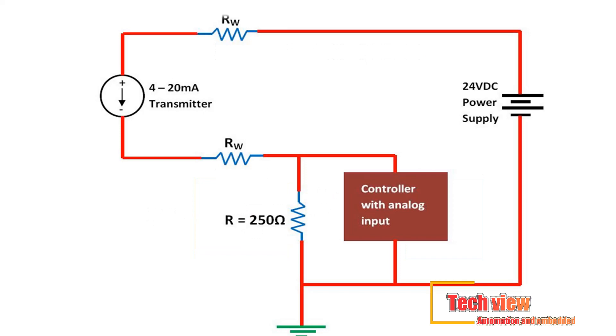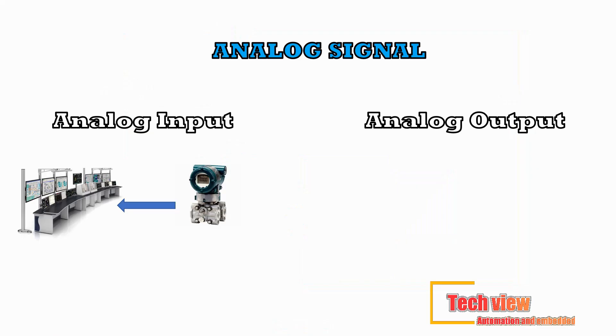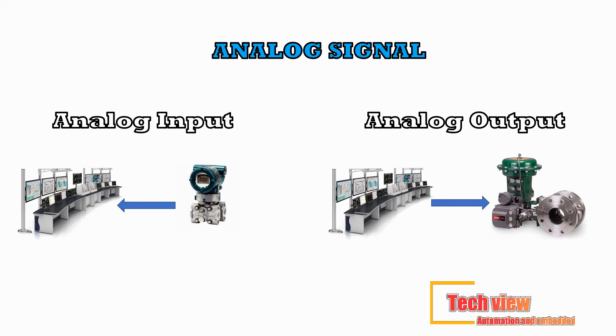The offset of 4 mA, in the case of a 4 to 20 milliamp signal, provides a distinction between zero signal represented by 4 milliamps and no information due to an open circuit. A temperature transducer is an example of an analog input device — it sends a continuous stream of temperature data to a PLC or DCS. This temperature data is expressed in varying degrees, not simply as hot or cold. An analog control valve is an example of an analog output device; it receives a continuous analog signal from a PLC telling it how much to open or close.